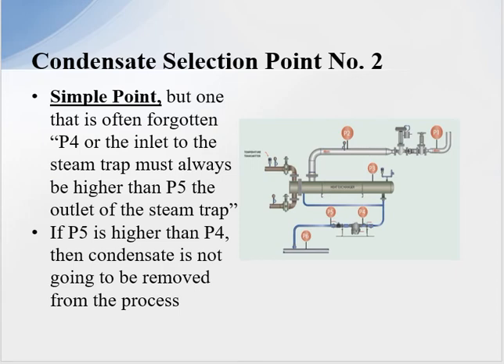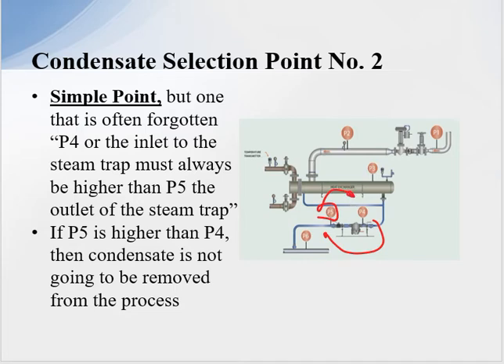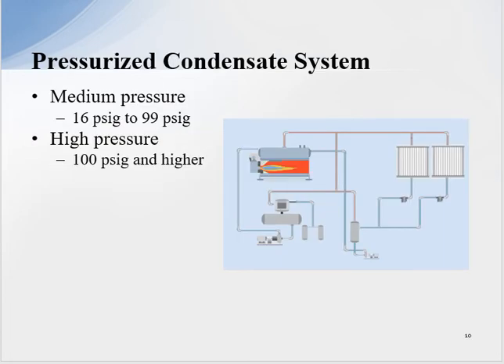The key principle is that as long as the inlet pressure is greater than the outlet pressure, life is good. If the outlet pressure is greater than the inlet pressure, then you need a condensate pump system.